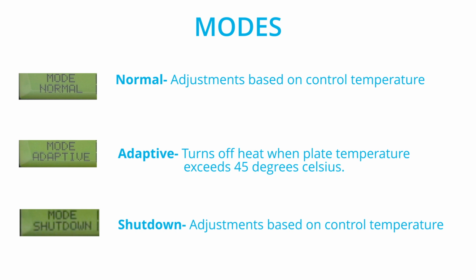This instrument has 3 modes of operation: normal, adaptive, and shutdown. The normal mode compares the temperature of the configured sensor, either RTD or thermocouple, with the set point to control the heater. In the adaptive mode, the sensor in the heated plate is used as the control trigger for the set point. A platinum sensor inside the plate monitors the plate temperature very precisely.